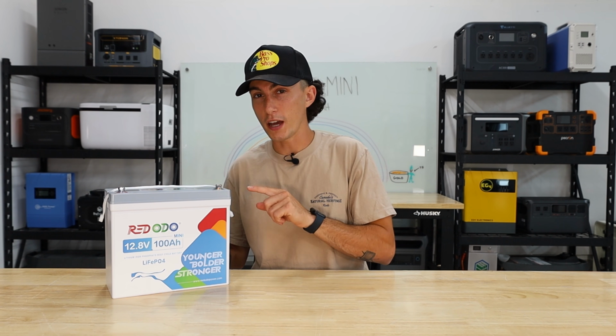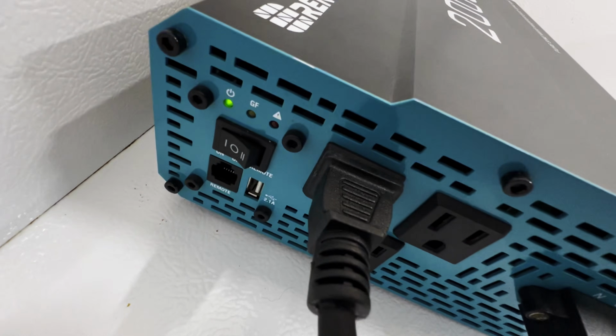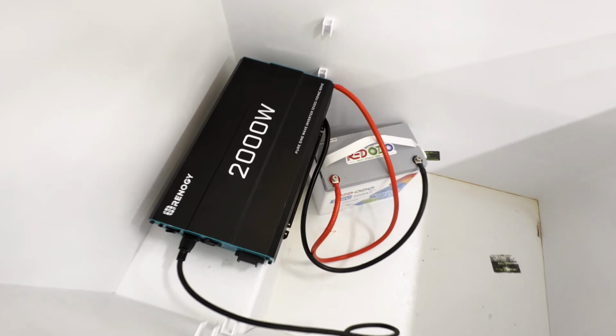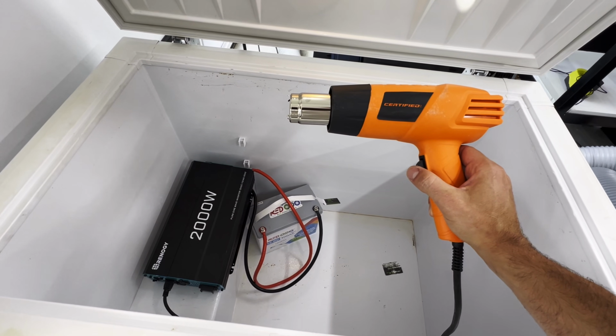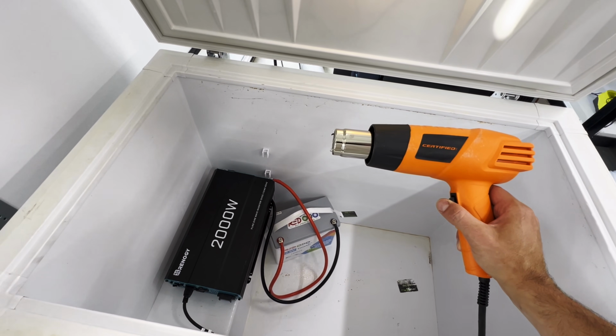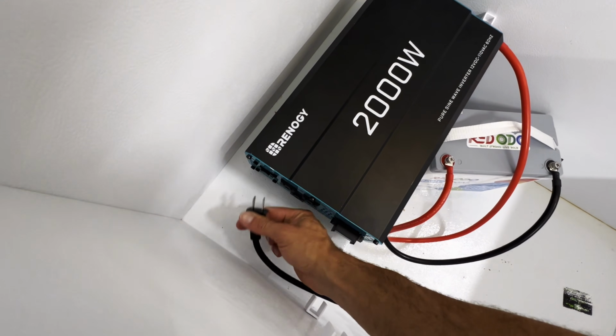This is the first battery we've ever done this test with that has not protected itself from the cold. Interestingly, when we tried to discharge it while it was freezing, it wouldn't work — so it was smart enough to know not to discharge when it was cold, but not smart enough to know not to charge when it was cold. I guess, like Redodo says, there is no cold weather protection, but it says the charging should get cut off before the discharging, and in our test it was the other way around.